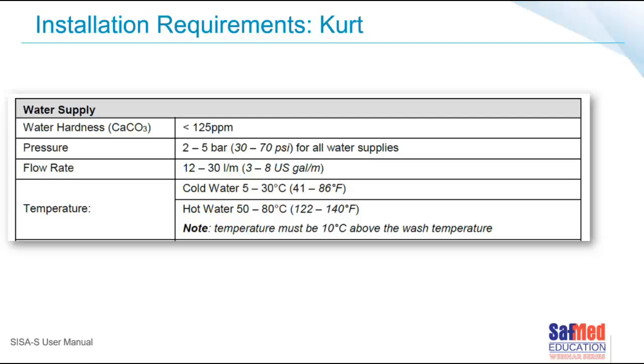Flow rate is the amount of water coming into the unit at a specific time, and that will also vary. Some of the ultrasonic cleaners have water level sensors, which we'll discuss later. If the water comes in too quickly, it will activate the sensors too early, or it will give you an overflow error, or it will stop the cycle. So all of these things are very important.